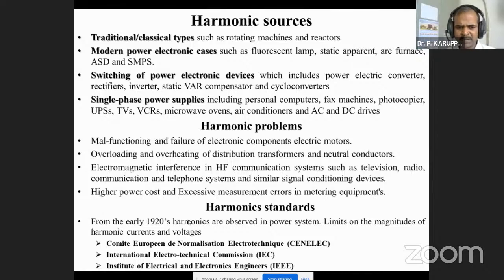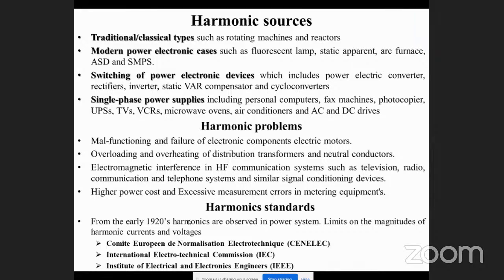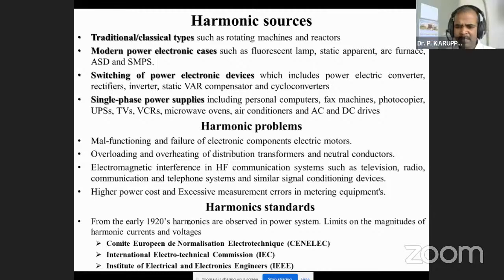Single phase power supplies like computers, fax machines, photocopiers, UPS, TV, VCR, microwave ovens, air conditioners, AC to DC and DC drives - almost all the equipment we deal with as loads introduce harmonic problems. Due to harmonic problems, we end up paying more electricity, which is common.